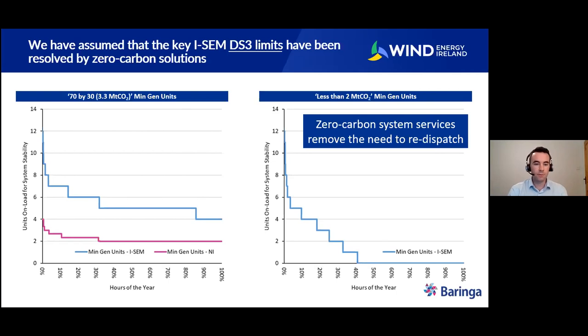In our 70 by 30 scenario, we had a minimum amount of thermal units that needed to be online of 4 units in Ireland and 2 units in Northern Ireland. If you can remove that need by having enough batteries, demand response, or synchronous condensers on the grid, you remove the need to have those units on the system to provide services, and instead only have thermal units online when they need to provide energy.